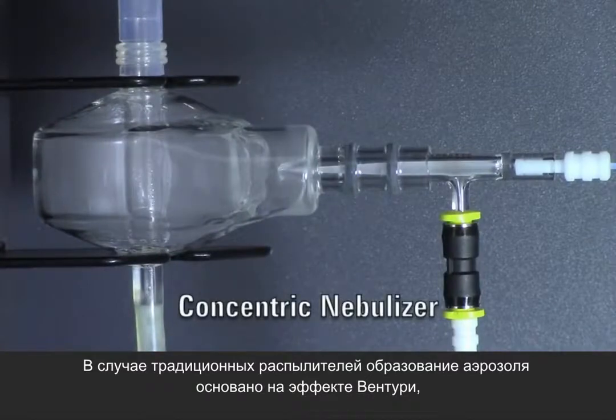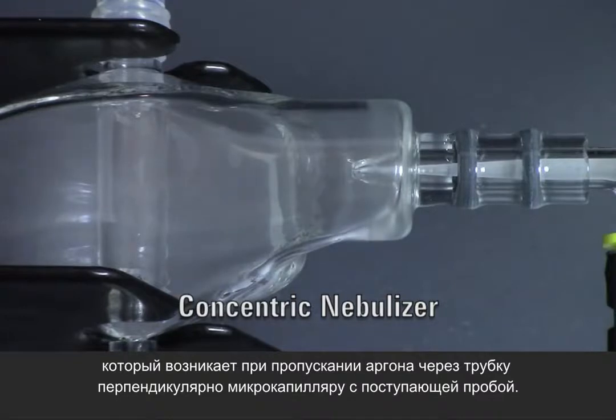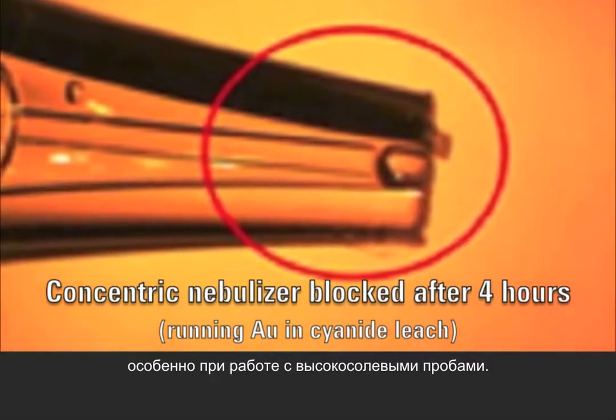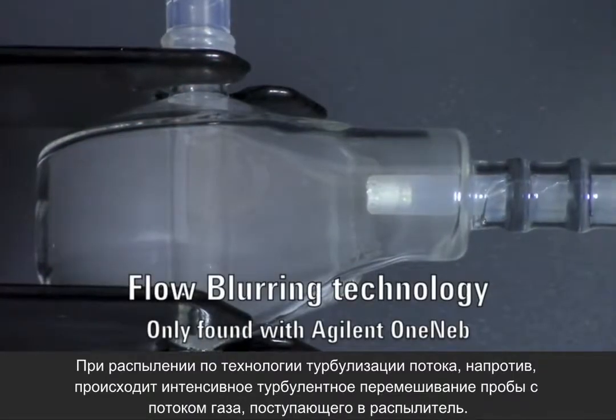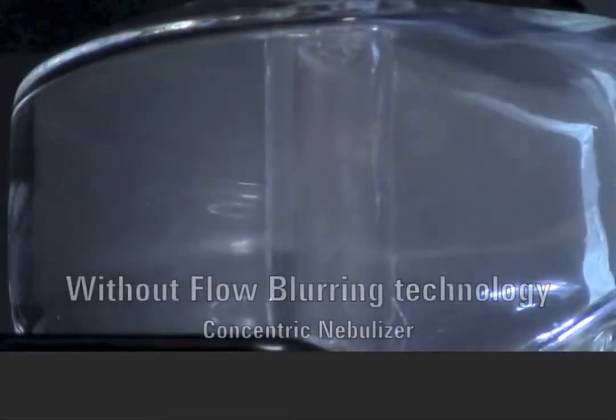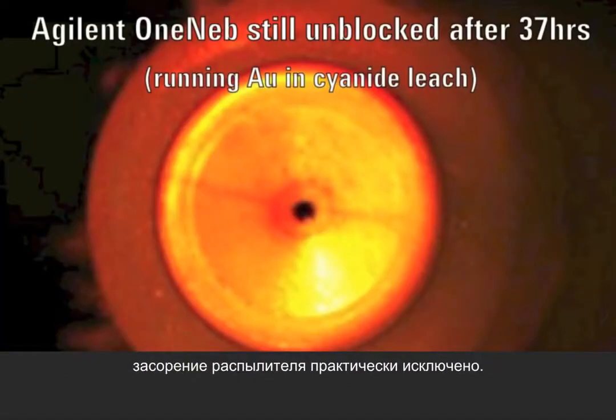Conventional nebulizers rely on the Venturi effect to produce an aerosol, as argon is forced through the tip past the narrow bore sample capillary. Not surprisingly, the narrow bore capillary is prone to blockages, especially with samples containing high levels of dissolved solids. In contrast, flow blurring nebulization uses highly turbulent mixing between the nebulizer gas flow and the sample, with no pressure drop and a constant diameter capillary — nebulizer blockage is virtually eliminated.